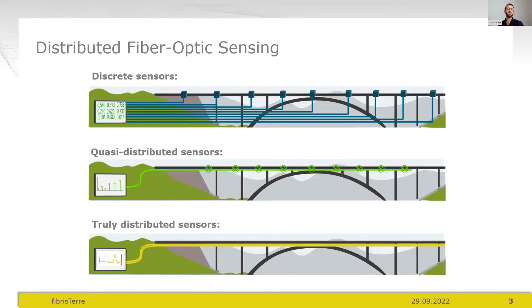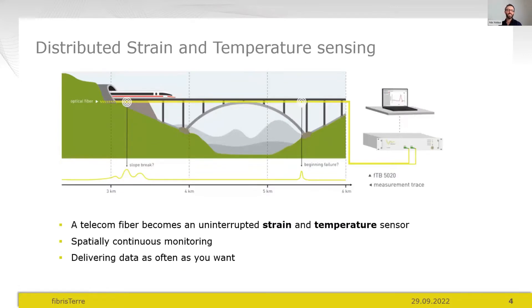From that, we come to truly distributed sensors — fibre optic sensing as we present it today. An optical fibre as used for telecommunication becomes a sensor, but this time a spatially continuous one. Every position along the fibre contributes to the data. The specific technology is distributed strain and temperature sensing, referred to as DSTS or distributed Brillouin sensing, delivering uninterrupted, spatially continuous monitoring in 24/7 operation or periodic plug-in use.